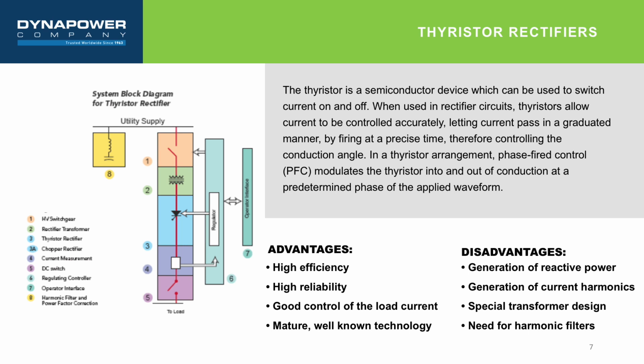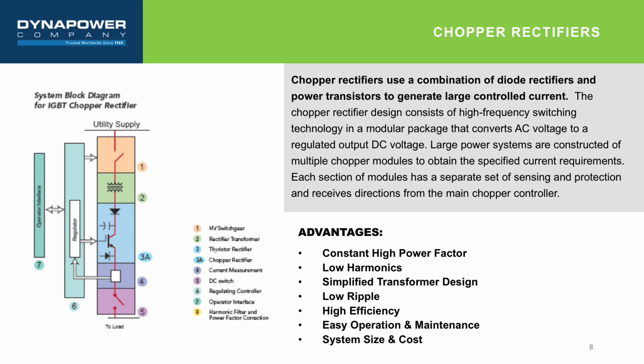The disadvantages are generation of reactive power, generation of current harmonics, special transformer design, and the need for harmonic filters. Chopper rectifiers. Chopper rectifiers use a combination of diode rectifiers and power transistors to generate large controlled current.